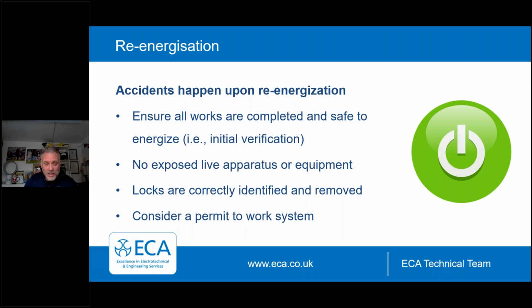Also consider a permit to work to confirm you've gone through these tests - effectively backward engineering to where you were at the start, making sure everything is safe for re-energization, and that you're correctly re-energizing the correct circuit. That's okay if you've got one circuit shut off in the whole enterprise, but with new installations you might have a selection of circuits energized and others locked off - you want to ensure you get the correct point of isolation and unlock the correct circuit, so as not to injure yourself and others.